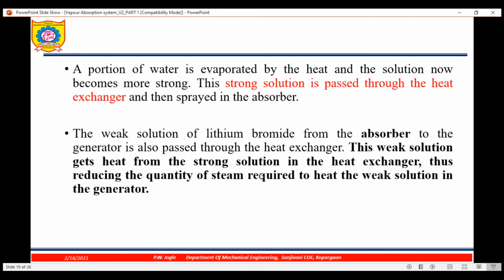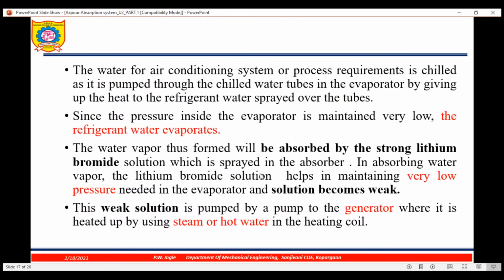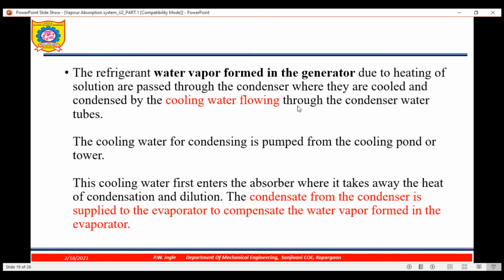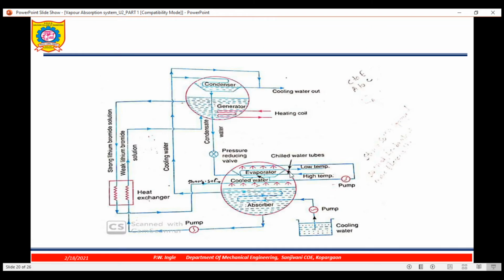Okay, so I will read that statement. The water for the air conditioning system or process requirement is chilled as it is pumped through the chilled water tube in the evaporator by giving up its heat to refrigerant water sprayed over the tube. Inside this tube, this is the chilled water tube, and over this we are spreading the water as a refrigerant. This water is used for the process, and again water is used as the refrigerant. This water will be sprayed over this water tube and will get evaporated.